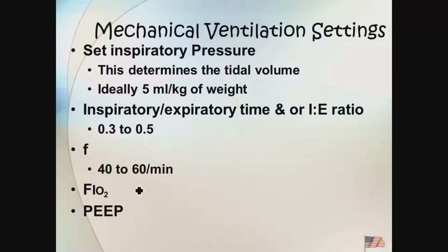Okay. Typically, most of the ventilators we're going to see in the neonatal world are what we're going to call time-cycled pressure-limited ventilation. Oh my God, what did he just say? Yeah. We fix the amount of pressure. We fix the amount of time that pressure is applied, and we monitor the tidal volume that it generates. So I'm going to set it to a pressure that's going to give me a tidal volume right around 5 milliliters per kilogram of body weight. Now notice I didn't say the ideal body weight, because in a neonate, their body weight is their body weight. They're so small. So if I have a 2 kilo kid, I've got a big kid there. Let's say I've got a 1 kilo kid. I'm going to have him trying to get a desired tidal volume of about 5 milliliters. Think of your syringes. Think how big 5 milliliters is. There isn't a lot of room for error.